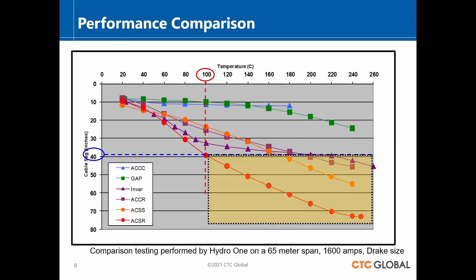The point I want to show here is that even these advanced conductors, including ACSS, before they get out to their full amperage, before they get to 1500 at the endpoint, have already sagged enough that, were they on the same tower, they couldn't continue to operate. You'd have to stop because they would now be violating their clearances to the ground, except for two. There are two conductors that Hydro One said are well up, even all the way out to their endpoints. They still don't sag down low enough. Those are truly low sag and can operate all the way up to their full amperage, which in those cases at the endpoints is about 2 times the power flow or the current flow as the ACSR had at 90C or 100C.